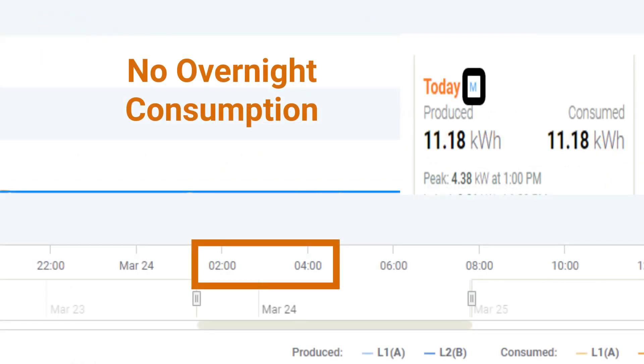Now let's talk about the second cause of CT mirroring. If you have identified mirroring of production and consumption but the overnight consumption is not being reported, this is an indication that the consumption CTs were enabled when commissioning the site but the CTs themselves are not physically present. If you have confirmed that the consumption CTs are physically on site but mirroring is occurring with no overnight consumption reflected, a site visit will be required to verify the installation of the consumption current transformers.